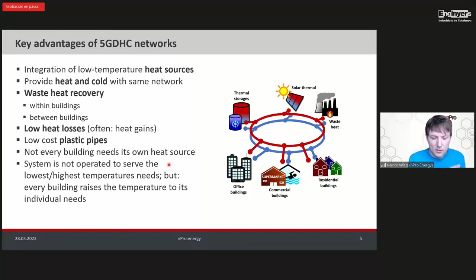I want to explain this waste heat recovery effect a bit more in detail to show the advantage here. We see the 5th generation district heating network with low temperatures, a warm pipe and a cold pipe, here in red and in blue. We have two buildings connected to it, and decentral heat pumps to supply the heat demand in the building.